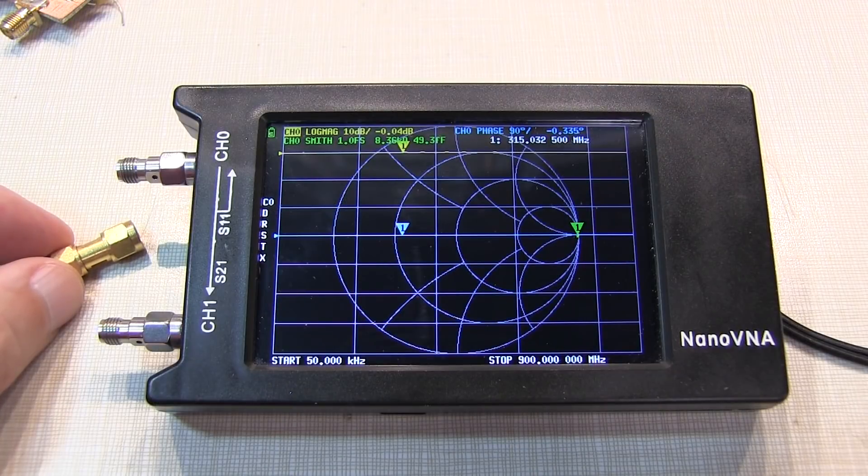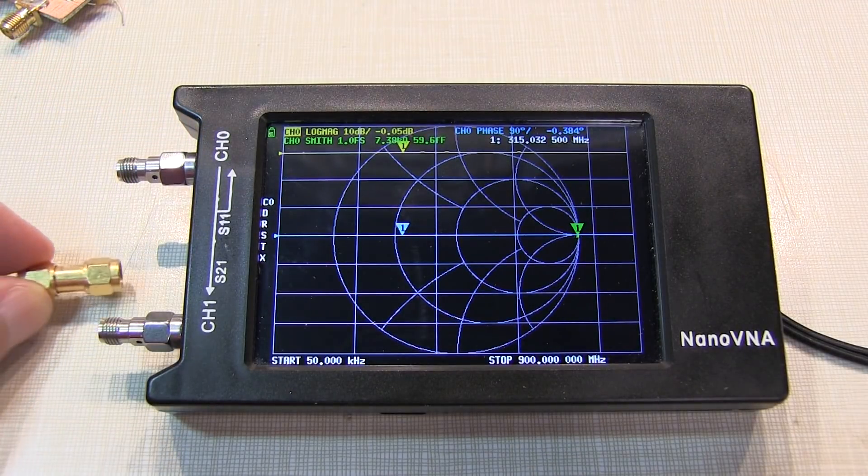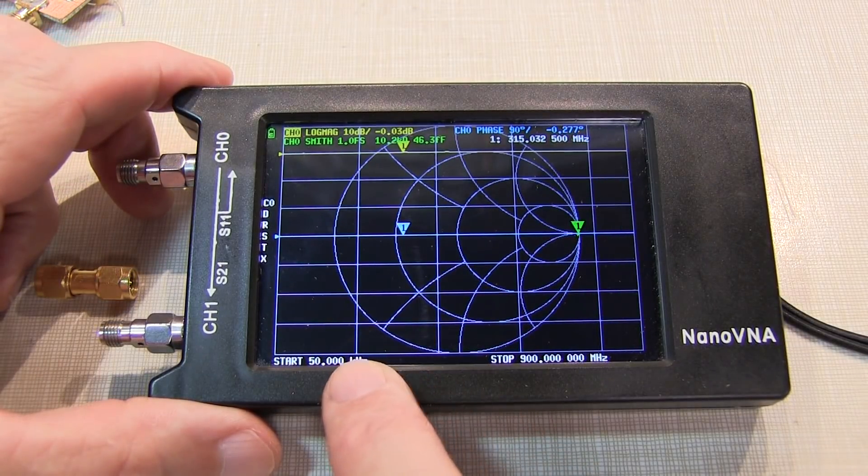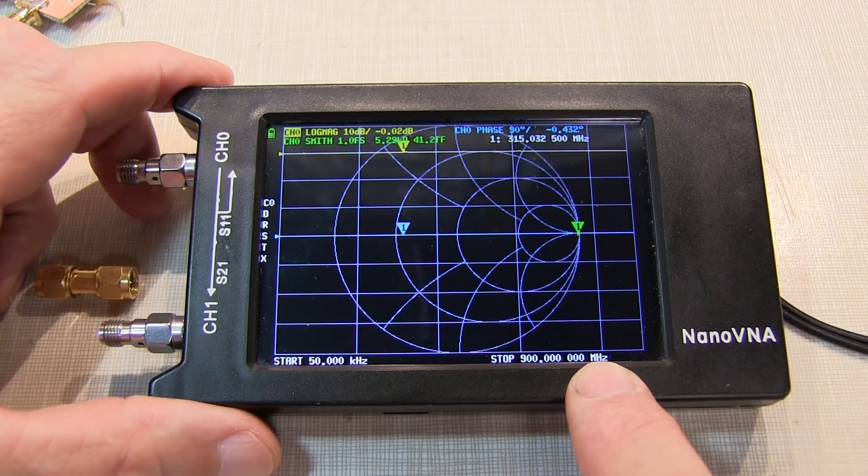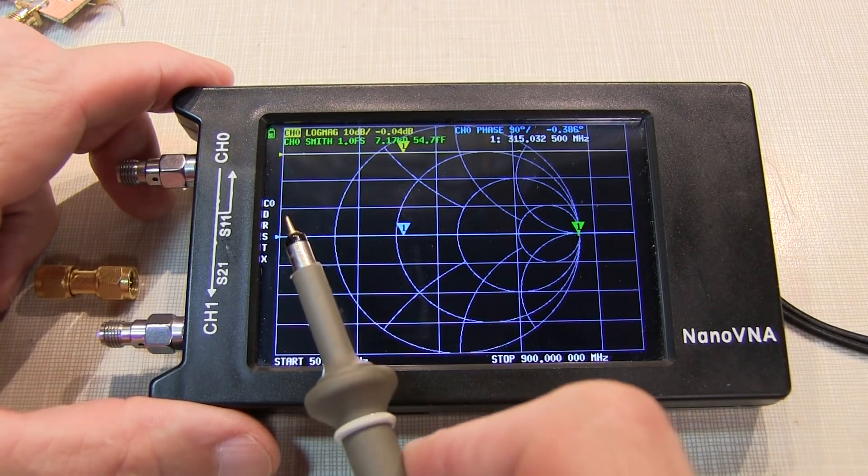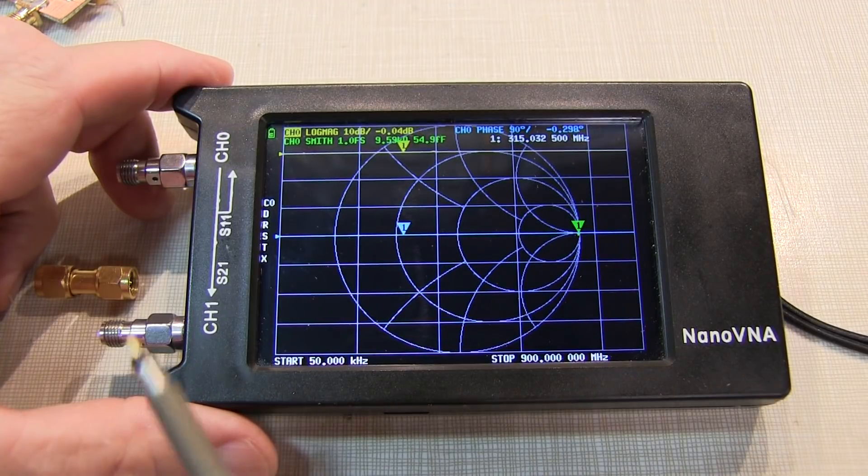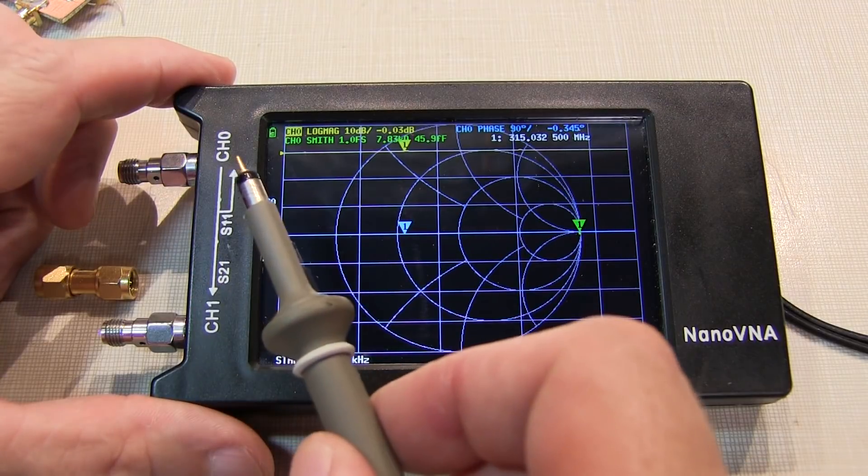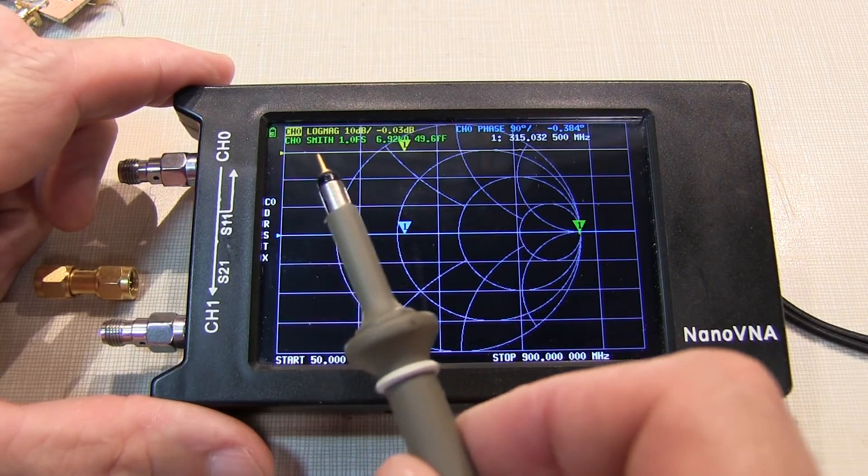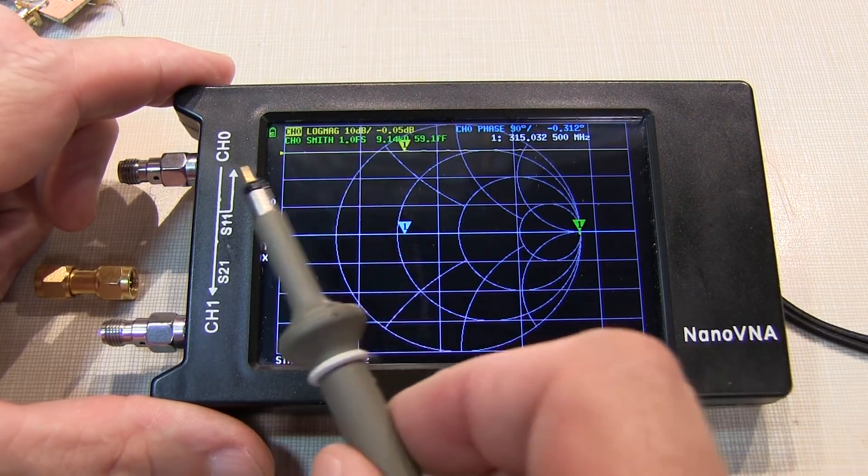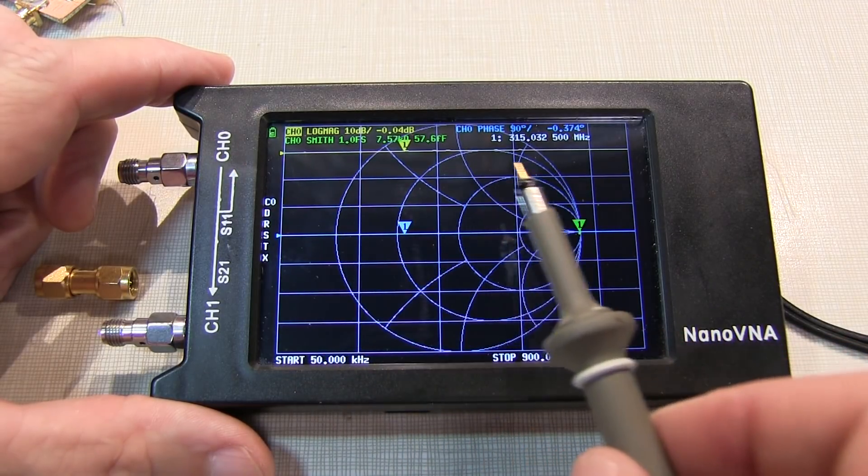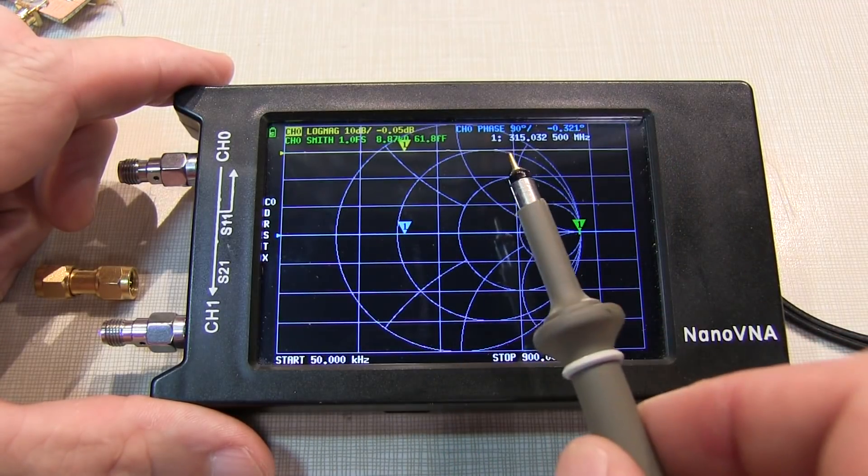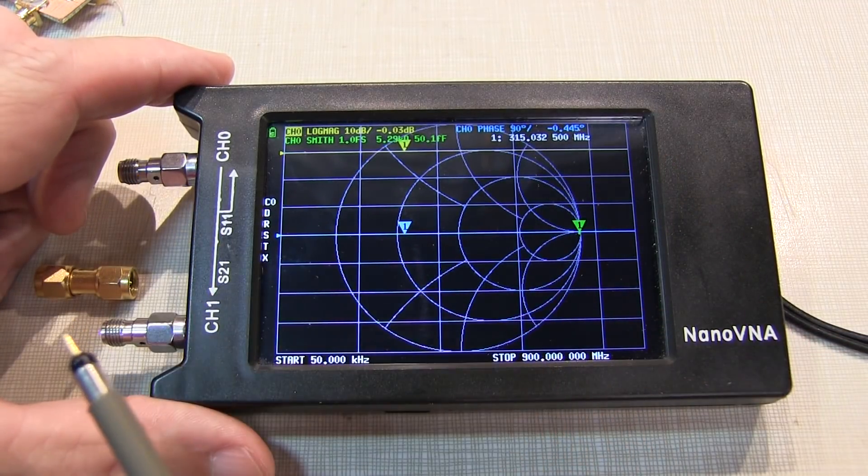Let's take a look at the effect an RF adapter would have on the complex impedance observed on the reflection port. Okay, the setup here is a 50 kHz to 900 MHz sweep, freshly calibrated, as indicated by the capital C for the calibration here. There's an open sitting here right now. And so, since we're only looking at the reflection properties, I just have three traces turned on. The log magnitude of the reflection coefficient, or S11, is riding here along the top, sitting at 0 dB across the whole frequency range, essentially a perfect reflection.